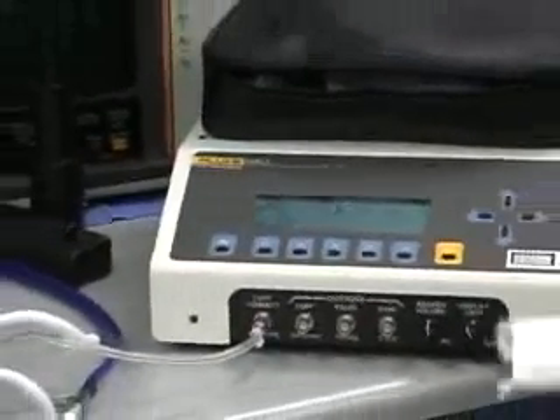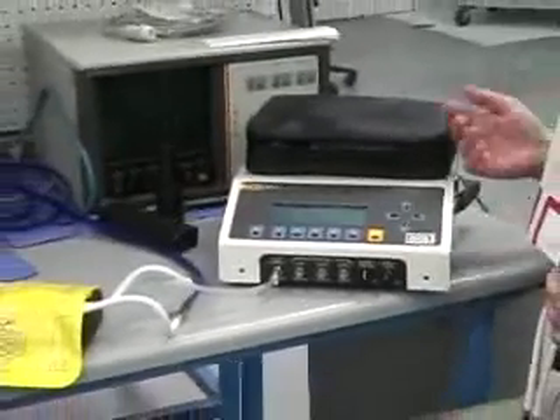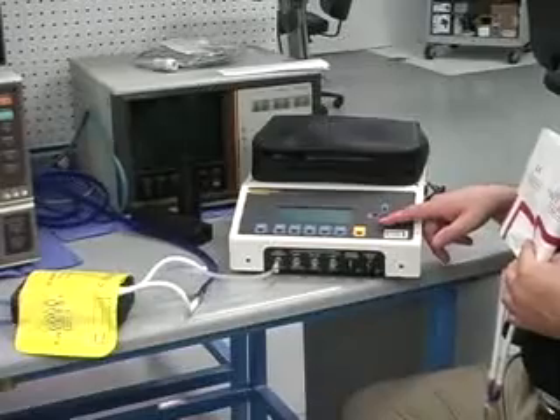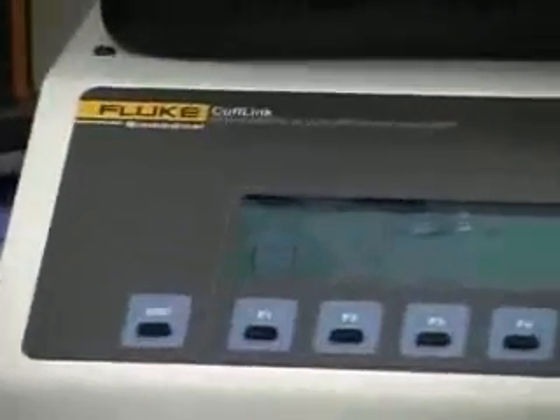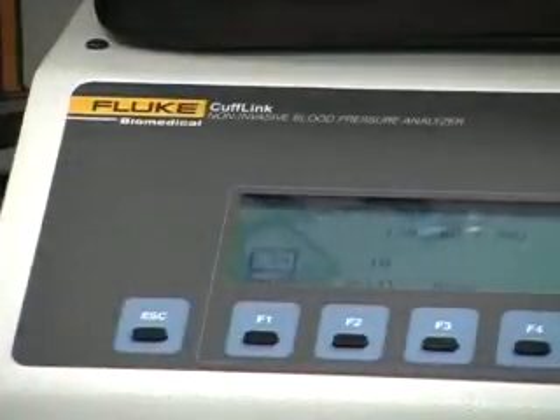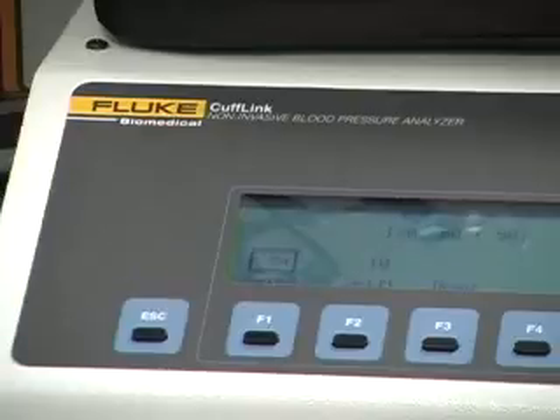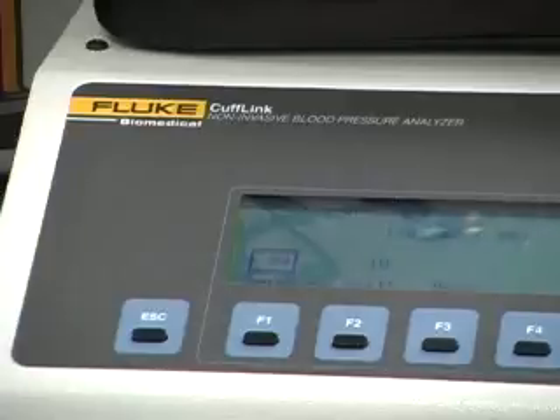Also, if they're having complaints about the monitor, like "I had problems getting a blood pressure," what you could do is lower the amplitude of the peripheral pulse and see what the sensitivity level of the monitor is. So instead of using 100% normal, use, let's say, 75% or 60%, and that would simulate someone that's in shock or has a very weak pulse. So their heart isn't beating quite as well, and they say, "Well, this monitor works great on healthy people, but when I put a sick person on it, I have problems with it." So let's simulate a sick patient and lower the amplitude of the pulse.